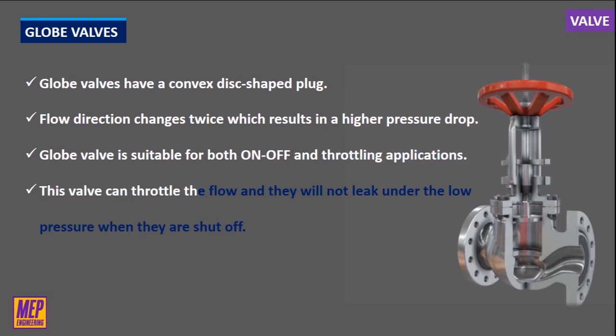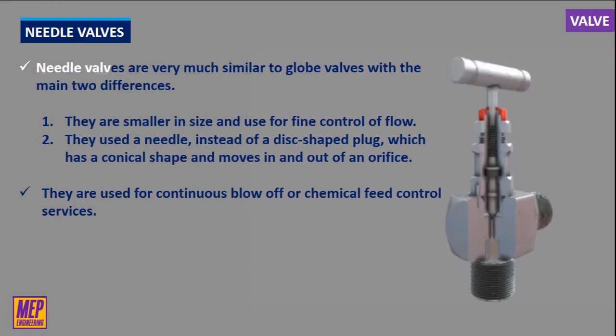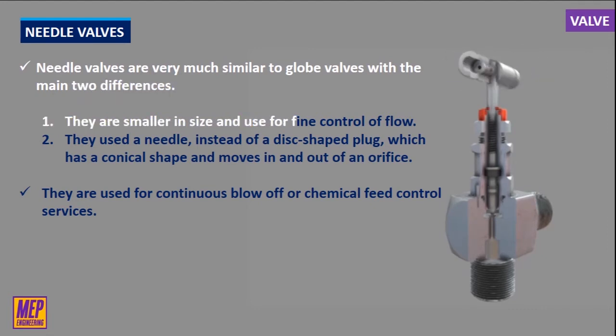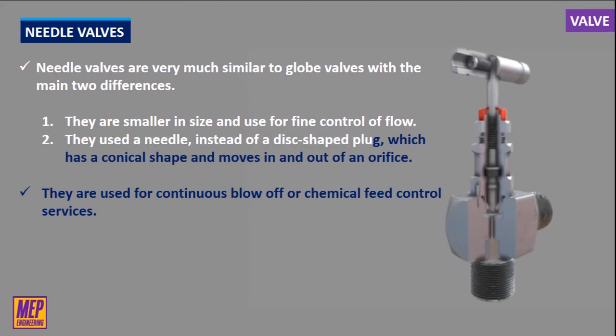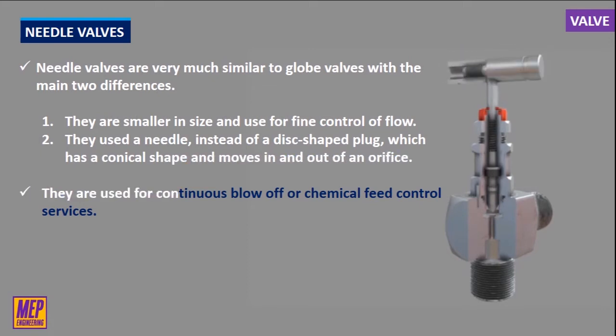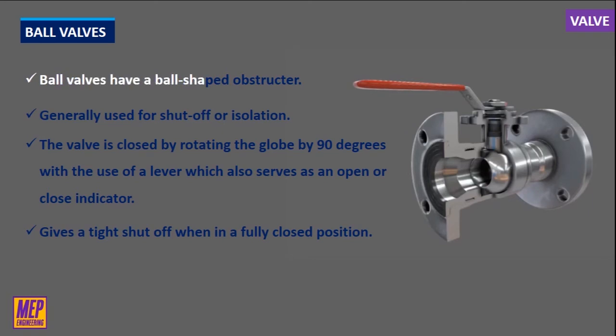Due to this type of construction, a globe valve is suitable for both on-off and throttling applications. This valve can throttle the flow and will not leak under low pressure when shut off. Needle valves are very similar to globe valves, with two main differences: they are smaller in size and used for fine control of flow, and they use a needle instead of a disc-shaped plug, which has a conical shape and moves in and out of an orifice. They are used for continuous blow-off or chemical feed control services.